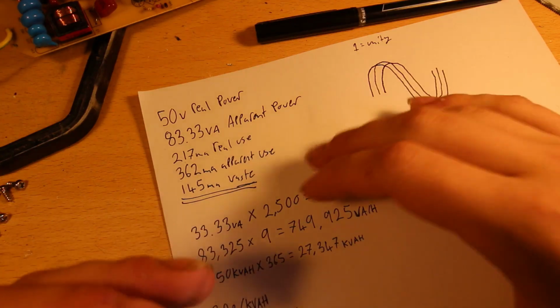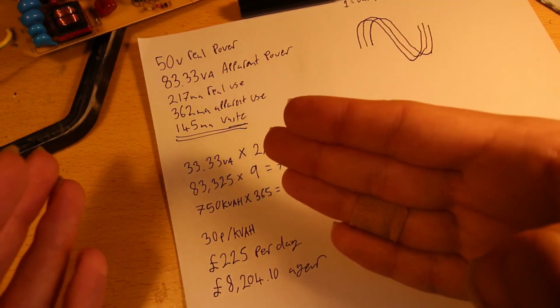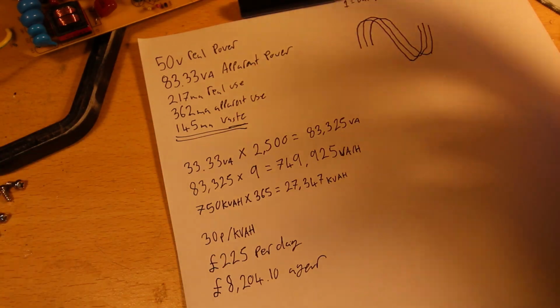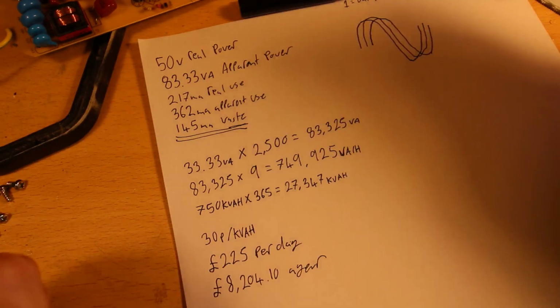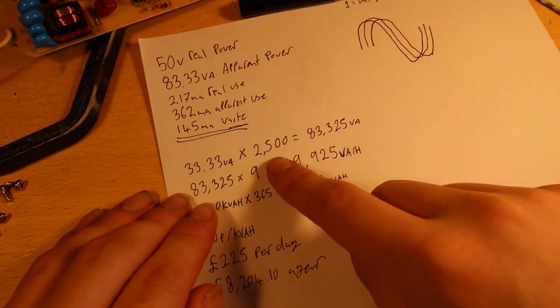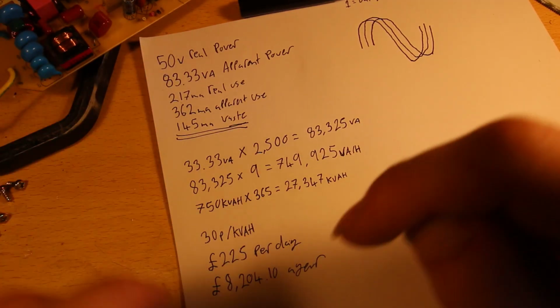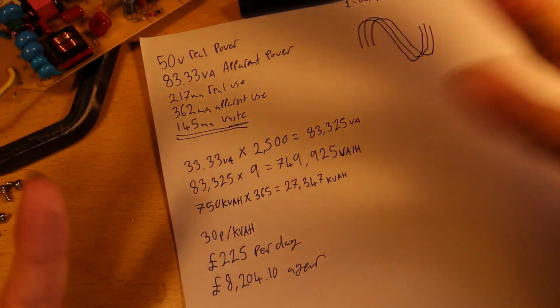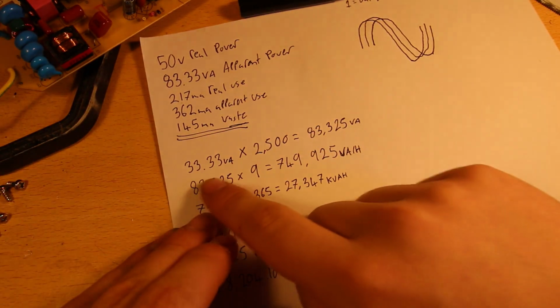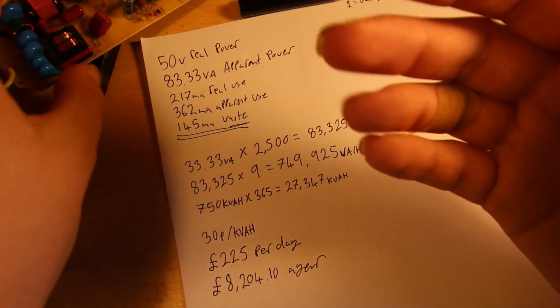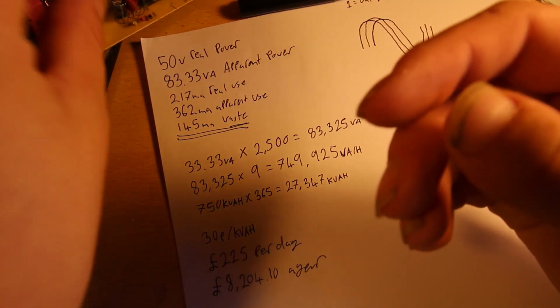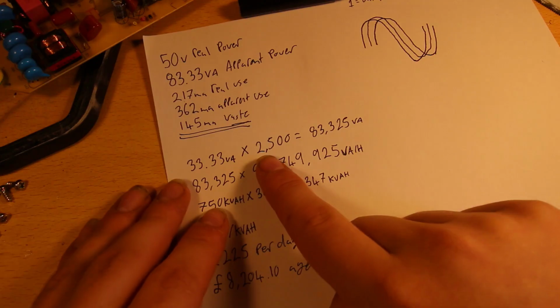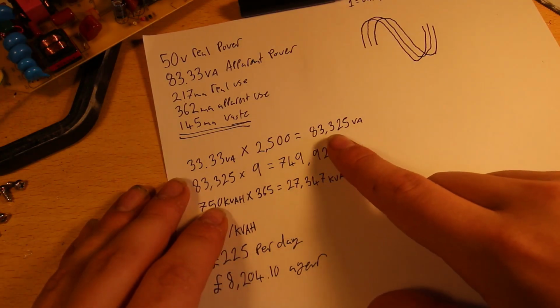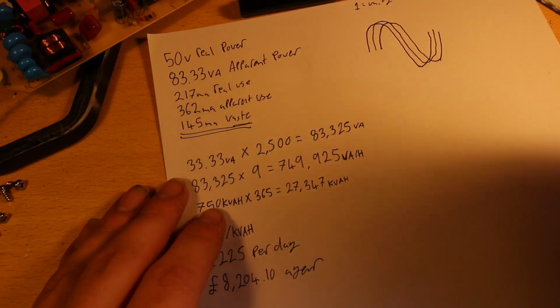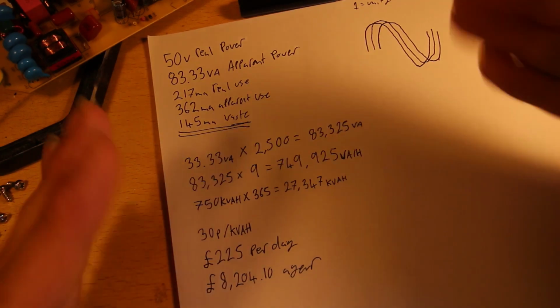So let's say you have a big campus, like a university or a shopping centre, a very big building, with 2,500 of these light fixtures around the campus, on for 9 hours a night to light the place up. If we take the 33.33 volt amp of unnecessary reactive power this would use with a non-power-factor-corrected supply, times our 2,500 lamps, that's 83,325 volt amp, or 83.325 kilovolt amp per hour.